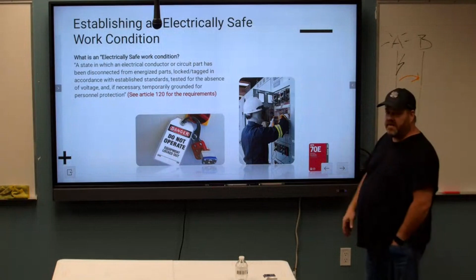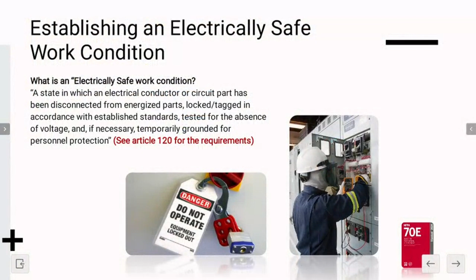That's normally where we play it. So again, an electrically safe work condition is where we've turned it off and locked it out, right? That's what we have to do. It's a requirement if it's 50 volts or higher.